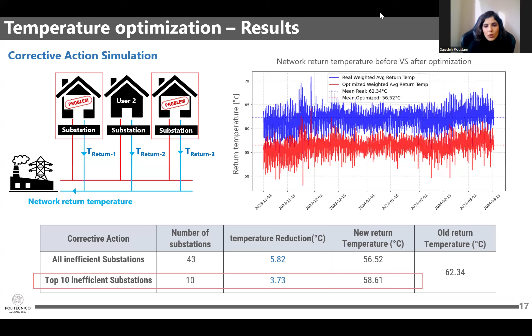We calculated it before and after applying these changes. As you can see in this graph, if we address this inefficiency, on average we are able to decrease the temperature of the network by almost 6 degrees, which is noticeable. However, economically it's not always possible to solve all inefficiencies inside the network. So we simulated addressing only the 10 most inefficient substations, and we are still able to decrease the temperature by 4 degrees, which is still noticeable.